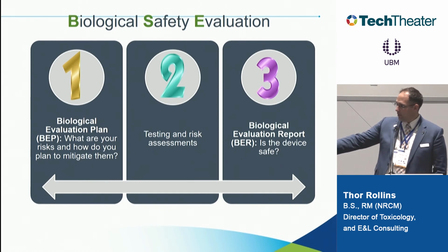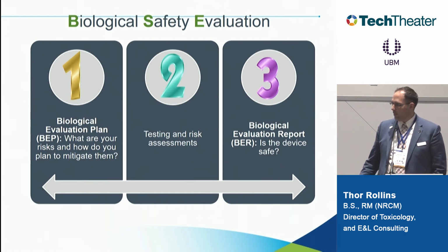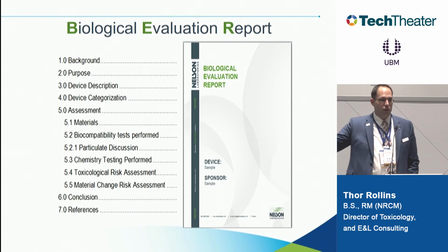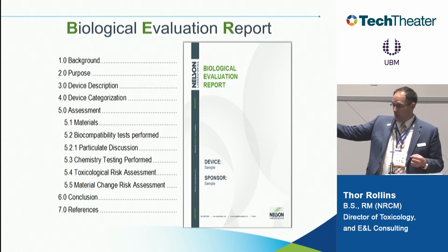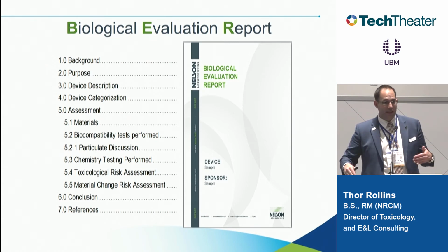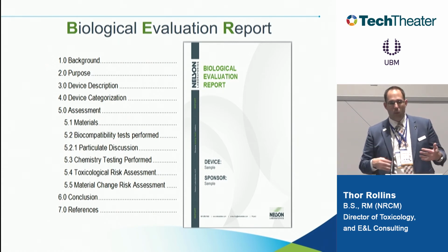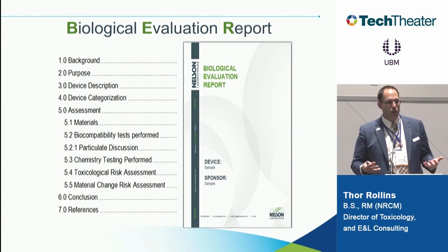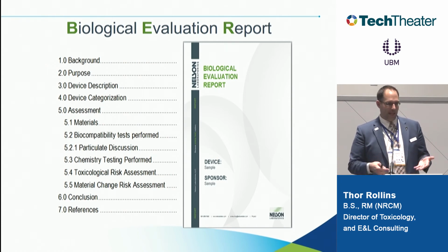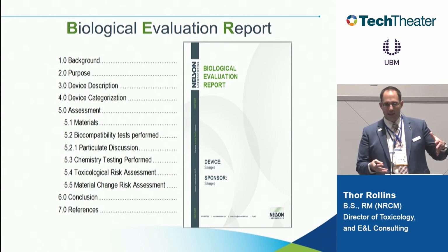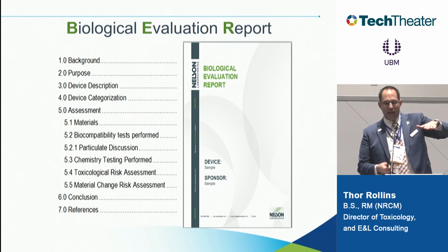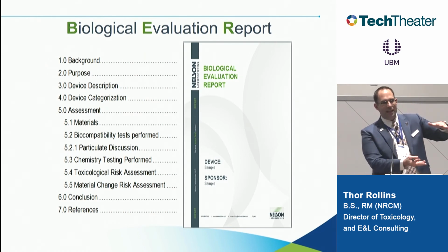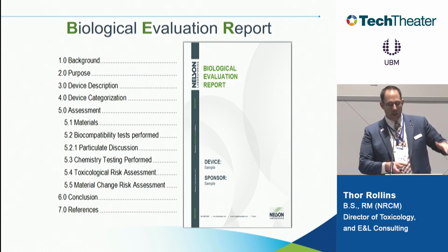So the last thing before I close up is this endpoint, which is coming up with a report. So this is our version of the report that we do if you contract through us. It basically walks through the initial risk assessment, what testing we did, what the results were, and then the conclusion is why we feel like this device is safe. So when you submit to the FDA, you have your initial plan, you have your test reports, and your BER, and that's your dossier that you submit to the FDA. Works really well.